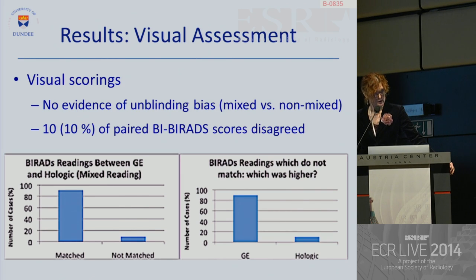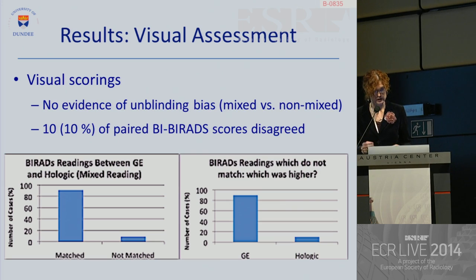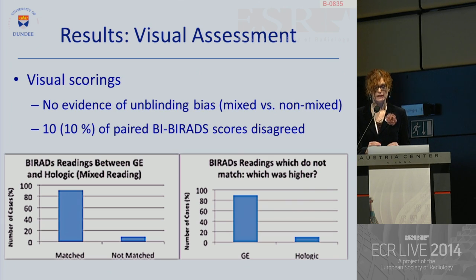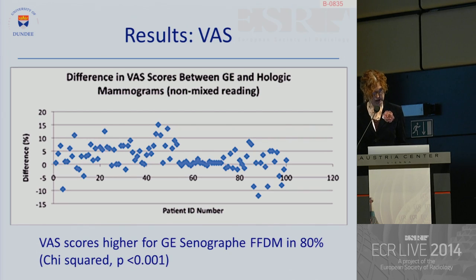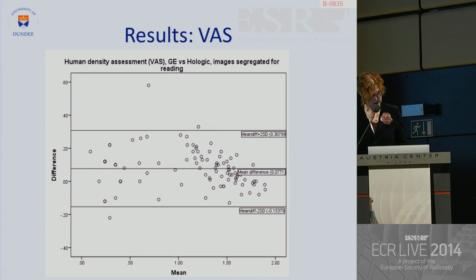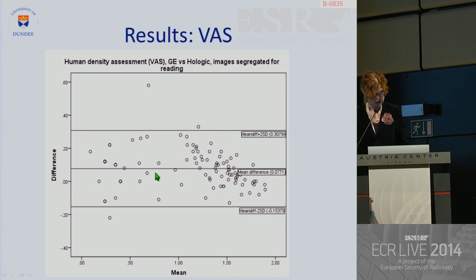Turning to the visual scorings: there was no evidence of unblinding bias — the expert observers perceived density the same whether they were reading a mixed batch or purely GE or Hologic. However, 10% of the BIRAD scores disagreed, and where they disagreed, the GE mammograms were perceived as being more dense in nearly all cases. The difference was usually only one score — the commonest was BIRADS 2 on GE and 1 on Selenia. The VAS scatter plot shows many more positive readings, indicating that the GE mammograms were perceived as a bit denser, and this is confirmed on the Bland-Altman plot, where there clearly is a systematic bias in favor of the GE mammograms.